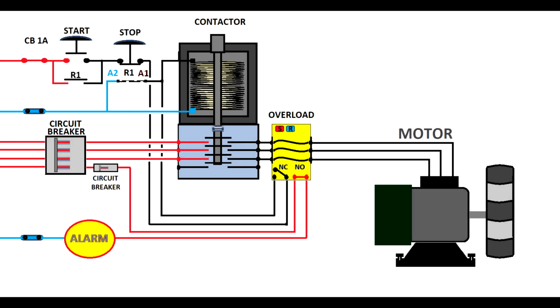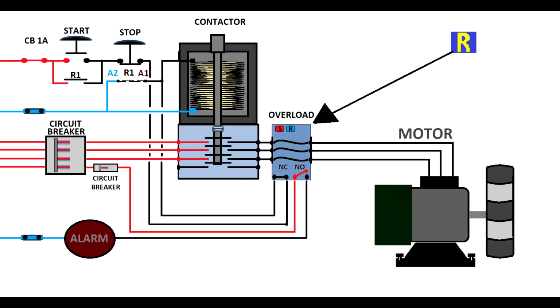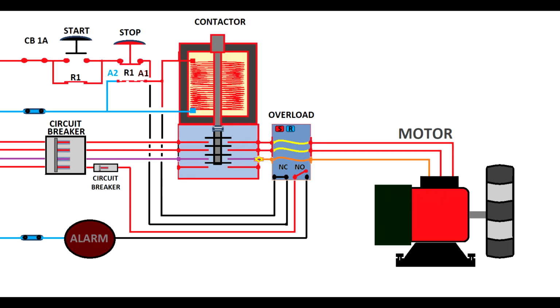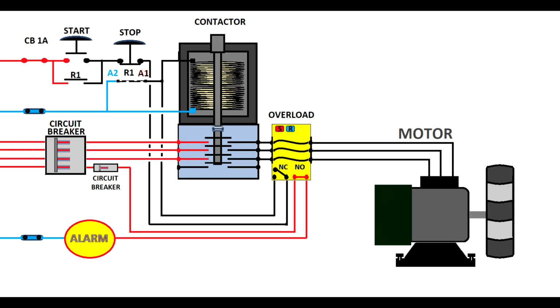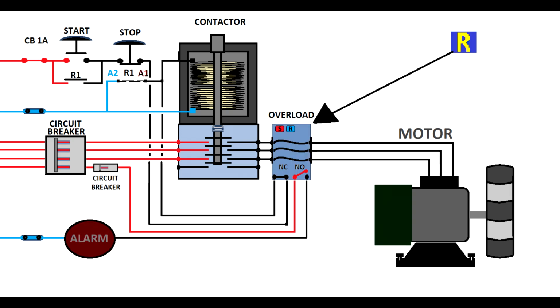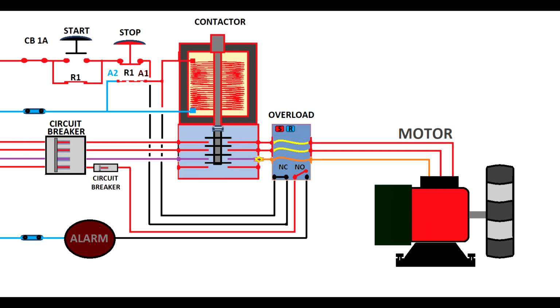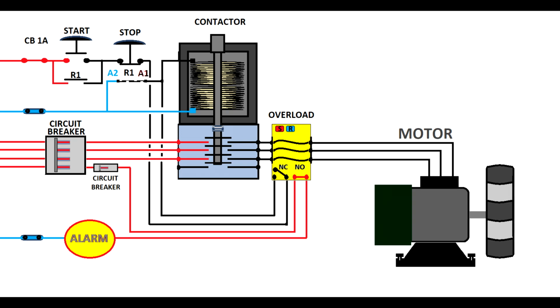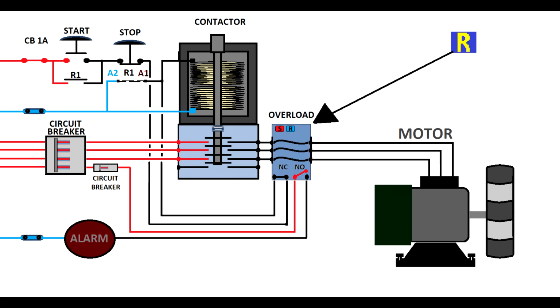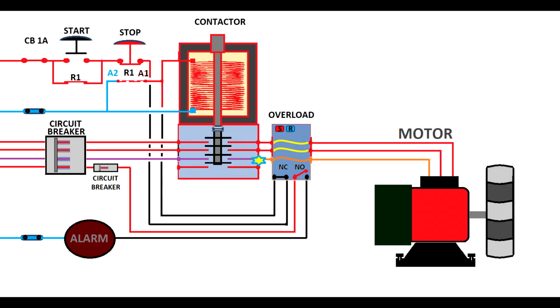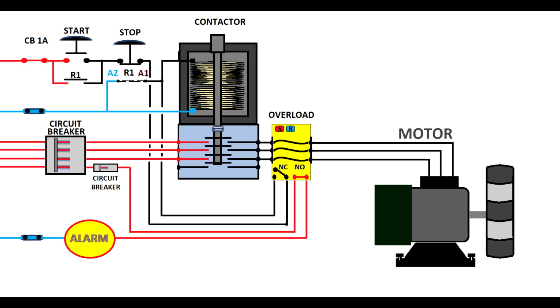Like you'll see now in this footage, you have an activated overload, you have an alarm, someone comes to your premises, and you reset the overload, ignoring the fact that the motor has some issues. Then in a couple of minutes the overload will trip again, and you will stop the motor, whatever it is, fan, pump, or anything. People are hoping that a miracle will happen, and then they reset it again. And the more you reset it, the time in between the overload tripping will be shorter and shorter, because the motor will be damaged more and more.